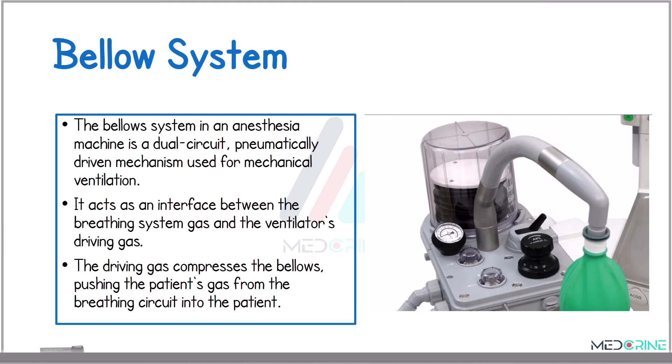The bellows system is part of the ventilator mechanism. This is a dual-circuit pneumatically driven system where the driving gas compresses the bellows, which in turn delivers the patient's gas into the lungs. This mimics normal ventilation and acts as an interface between the breathing system gas and the ventilator's driving gas.